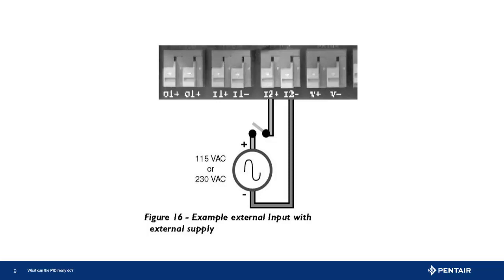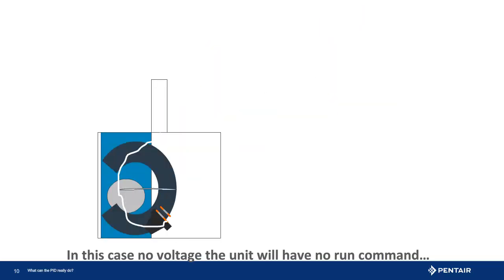Here we are using AC voltage being used to signal the drive to do what is programmed. And depending on what the control is, we need to program what the drive will do. For this example, let us look at a float switch. The control we are using is a normally open switch here. This is a good way to protect the pump if pulling from a tank or cistern. When the cistern is full of water, the float will rise to the point that the points will close, passing voltage. This can be referred to as a run command.